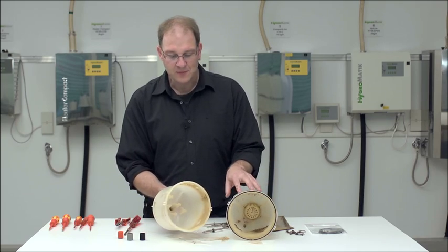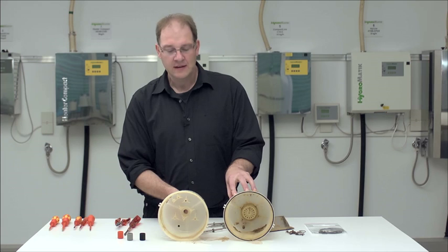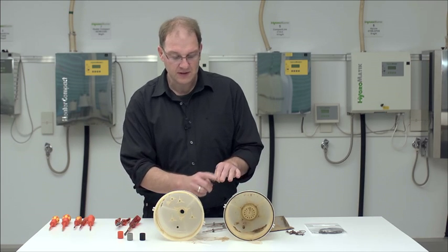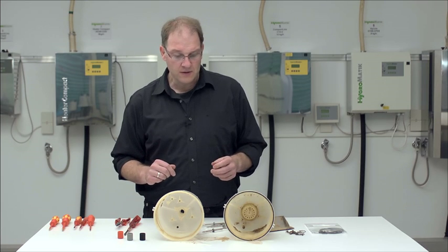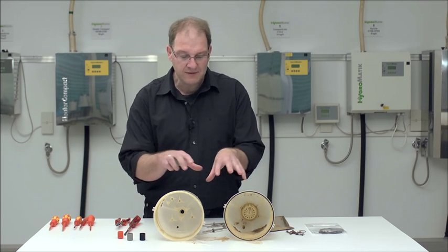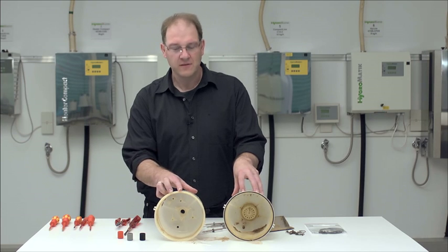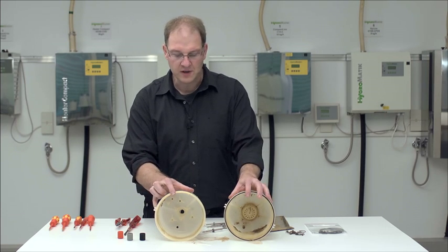When handling these electrode humidifiers, please don't use cleaning agents because the principle of these electrode humidifiers is to send an electric current through the water, and it would be disruptive if we had any chemicals in the water, because with them the generation of such a current would be severely disrupted.